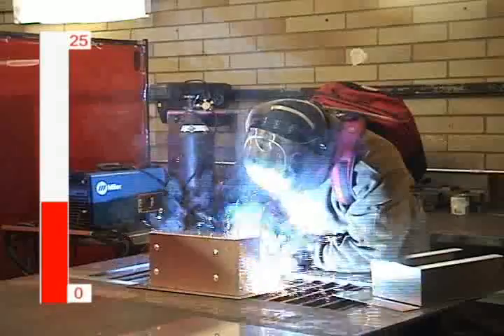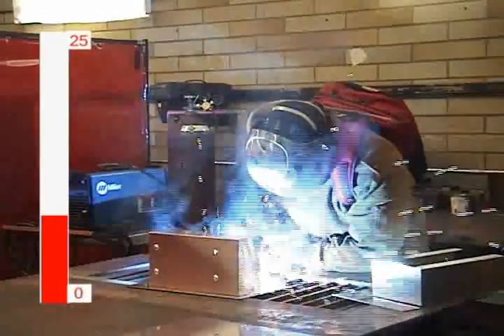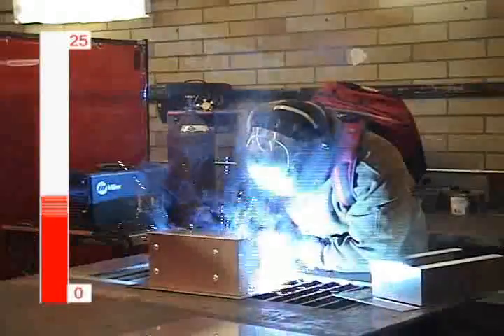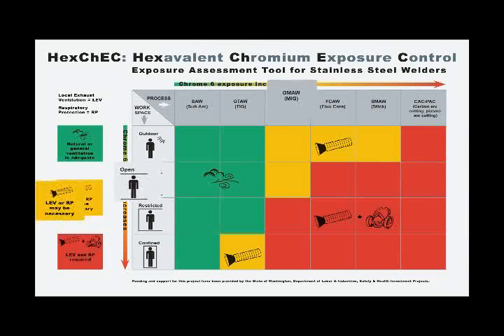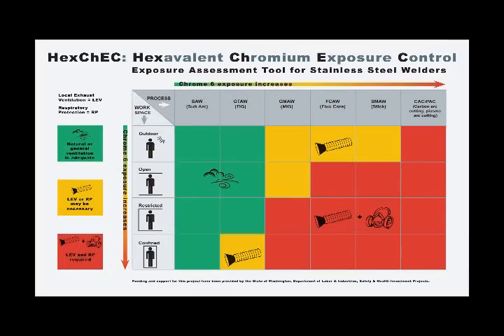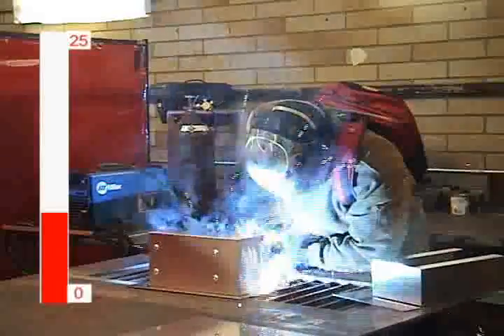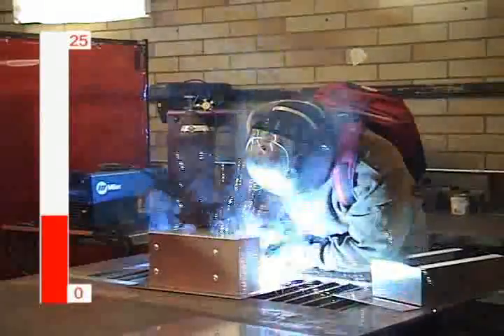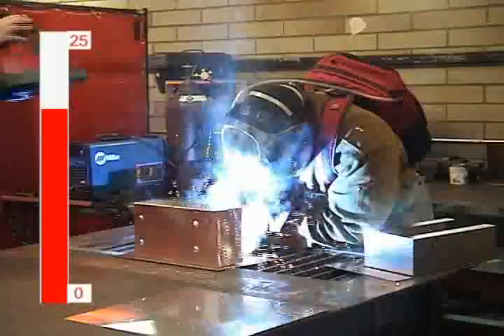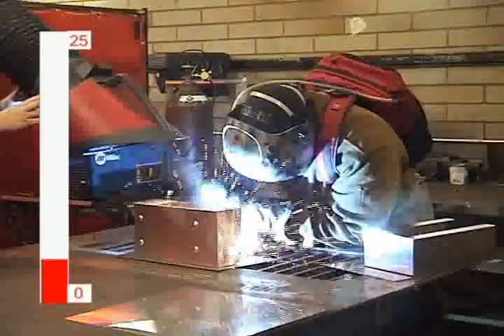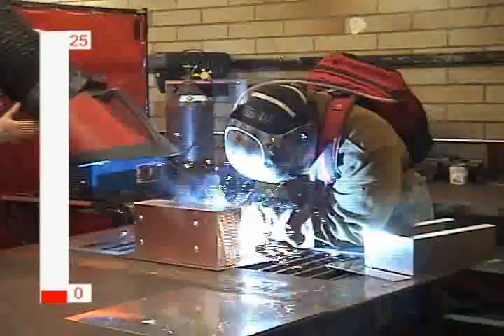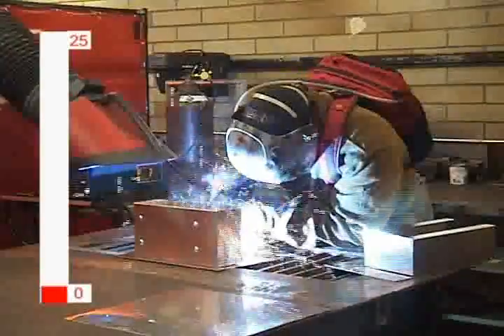In our second open space shop example, Justin MIG welds on stainless without using any LEV. MIG welding in an open space without LEV may be okay, but it depends on the natural and general ventilation of the space. According to the hazard assessment tool, LEV is recommended when MIG welding in a shop. If Justin were MIG welding in an area with restricted air flow or in a confined space, LEV would definitely be required. When we introduce a Lincoln Electric Mobiflex LEV hood to the side, his exposure to total welding fume is easily reduced to almost nothing.